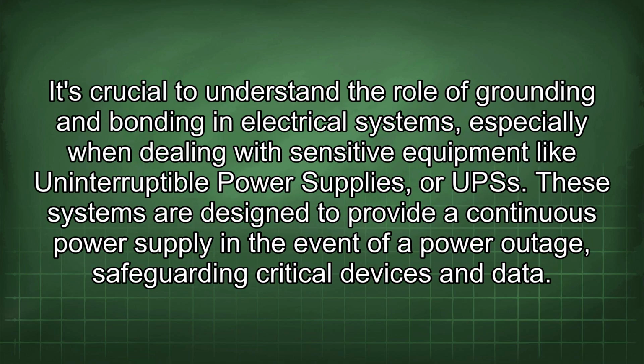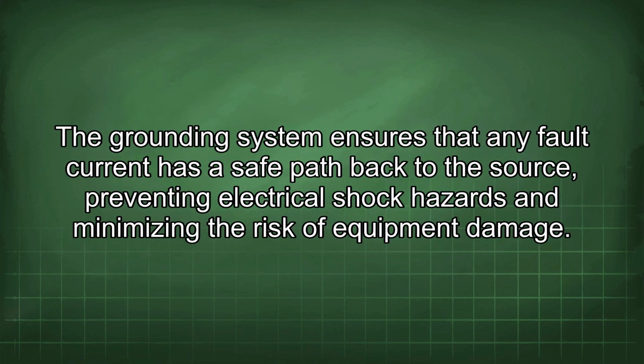It's crucial to understand the role of grounding and bonding in electrical systems, especially when dealing with sensitive equipment like uninterruptible power supplies, or UPSs. These systems are designed to provide a continuous power supply in the event of a power outage, safeguarding critical devices and data. The grounding system ensures that any fault current has a safe path back to the source, preventing electrical shock hazards and minimizing the risk of equipment damage.